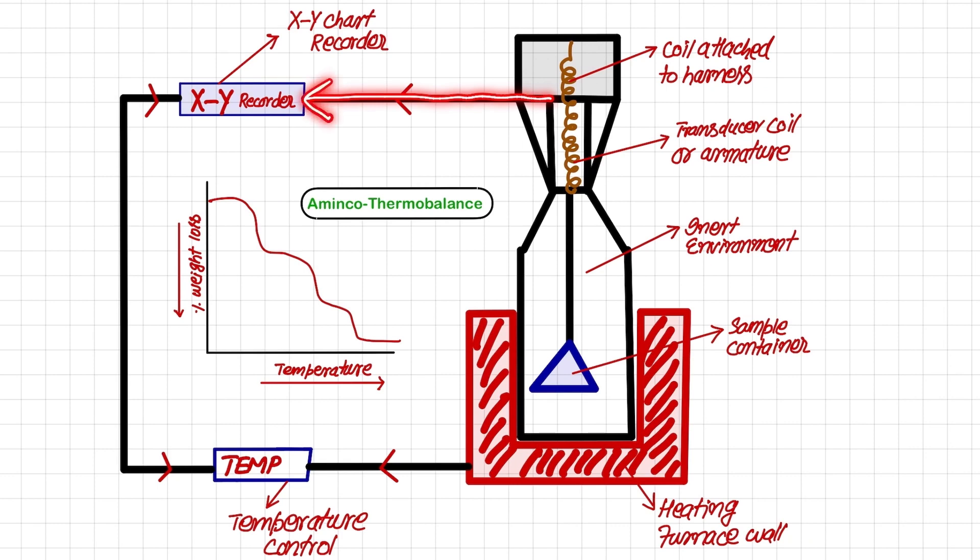That corresponding amount of current is fed to the XY chart recorder which will then make a graph. Similarly, the heating information is sent to the temperature control and this is further connected to the XY chart recorder. There are two types of information that this XY chart recorder records: first information coming from the furnace about the temperature, and the information from the current generated that is directly proportional to the weight change in the sample.